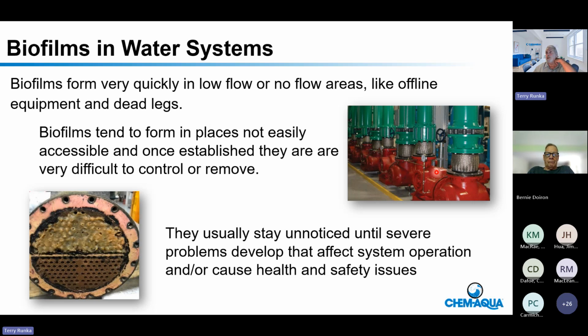There are lots of places for biofilms to form in a cooling system and a hot water distribution system. The problem is these systems are made out of glass, figuratively. We cannot see it, and by the time you find it, usually it's a chiller loaded up with bio, actually shut down because of the bio. You can imagine how much Legionella bacteria is in there, but you can only imagine it. You have to test to find out.